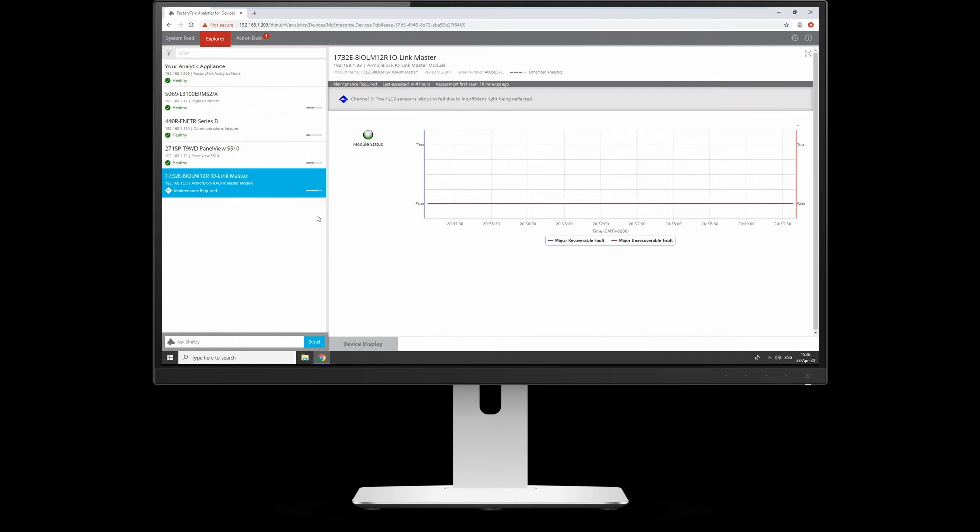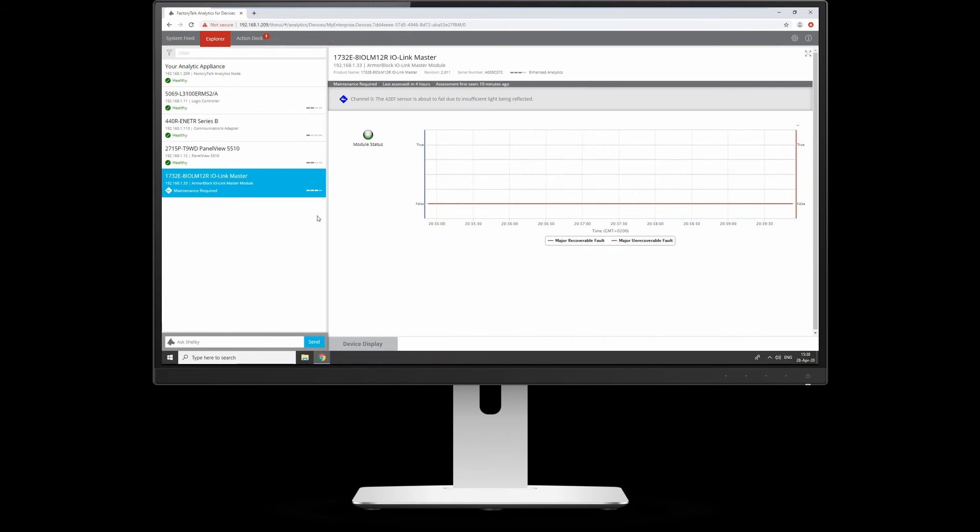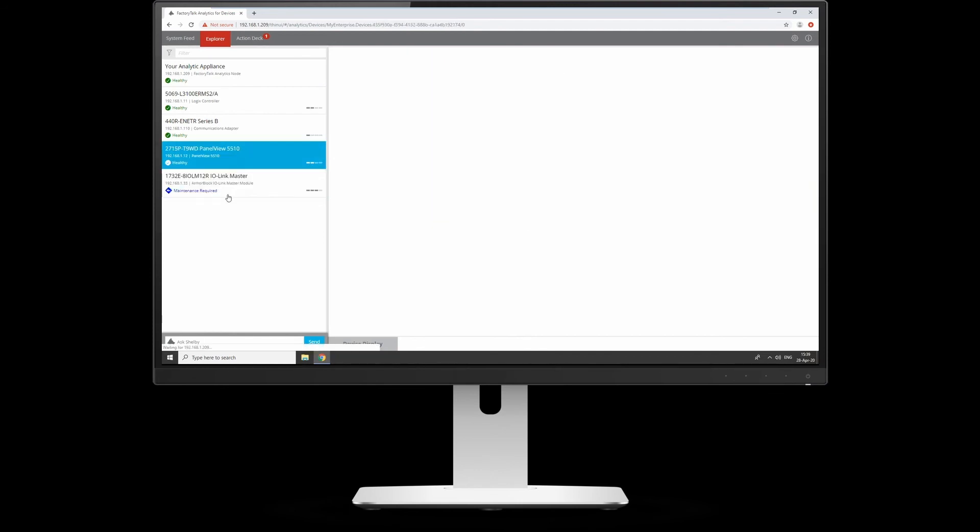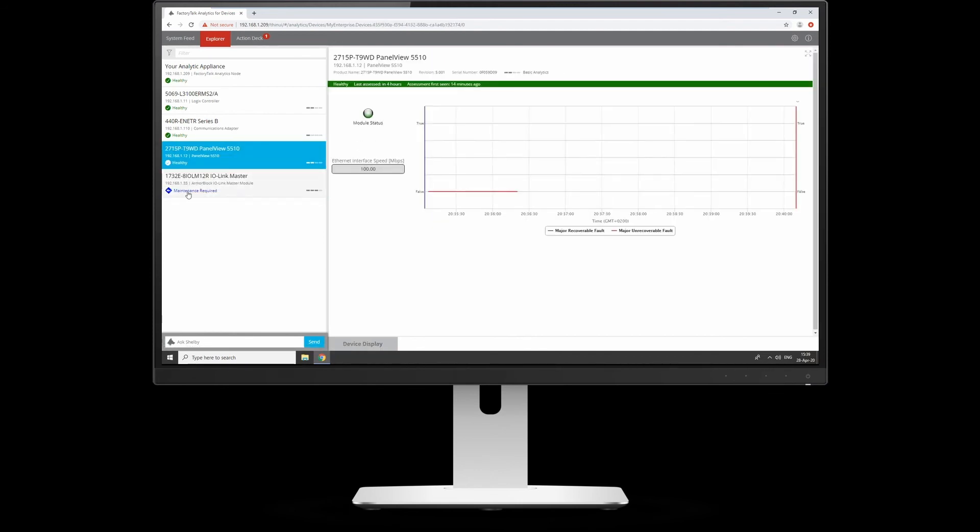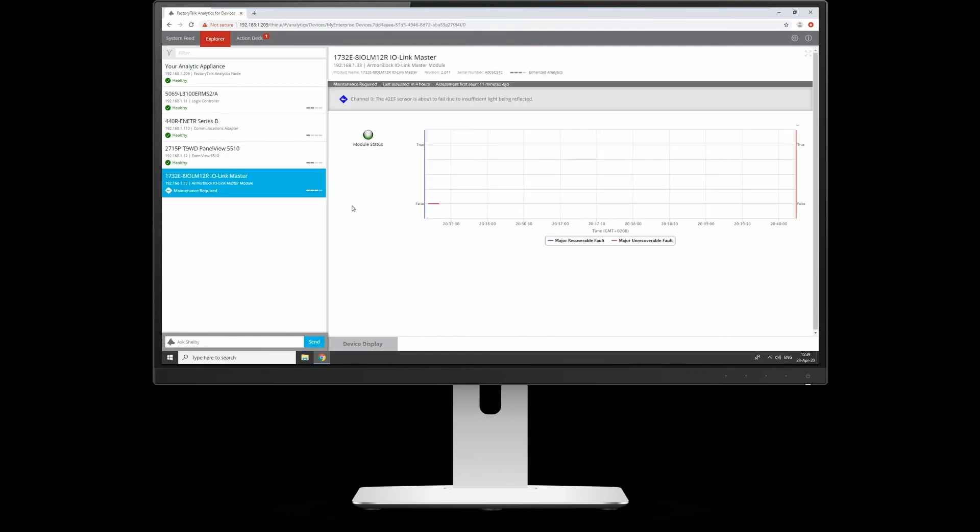Now if I go and unplug that sensor, you'll see that this box is not real time. It's not meant to replace alarming on your control system. It's a simple deploy supervisory system—it's additional to your alarm. You wouldn't expect to be waiting for this to tell you that your sensor's failed. But in a minute or two, you should see that will change to a higher level because the sensor's been disconnected.